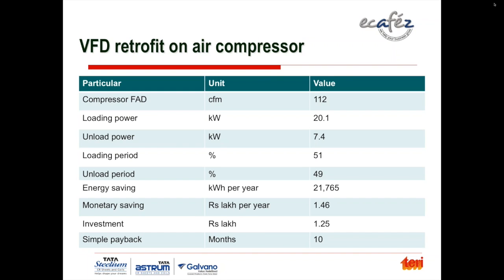And after you consult, because of some of the older models, the VFD cannot be retrofitted. Only the newer models can be retrofitted. Otherwise, if you are going to purchase a new air compressor, then it is definitely worth looking for a screw air compressor having VFD control also fitted in.